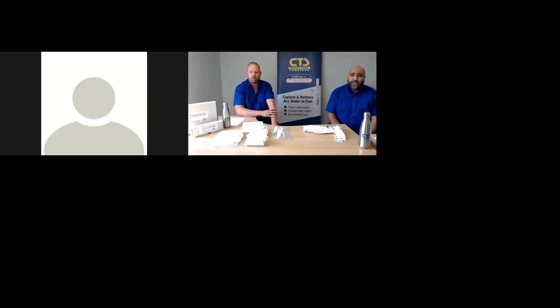That concludes our visual presentation. Thanks everyone for watching. We're just going to have a little look at the chat now for any questions. We've got one: what are the lab tests you have that meet the EN standards? Seibolt Laboratories in Sweden have done all the lab tests. We've got a lab test showing 100% effective at removing water to less than 64 parts per million in the sample. The reference sample started off at 363 parts per million and we managed to reduce that down to 64. When the sample was checked again after a week, it was down to less than 40 parts per million. Since then, there have been several thousand other tests done by Seibolt.